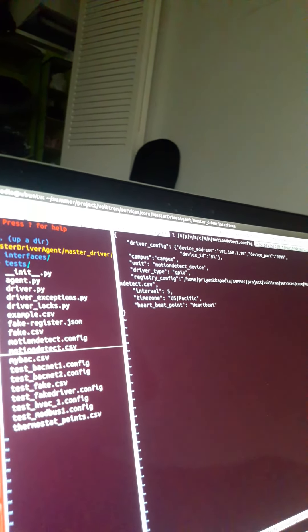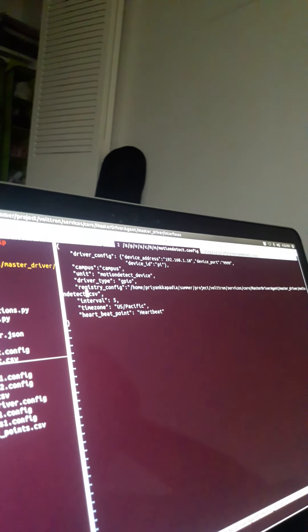So these point names are the request names which will be going to our socket server. There are three files: the master driver config file, the device configuration file, and the registry config file of that device where the point names are defined. File location doesn't matter because most of the time you are giving an absolute address, so as long as it's on the same machine and you have permissions you won't have any problems.